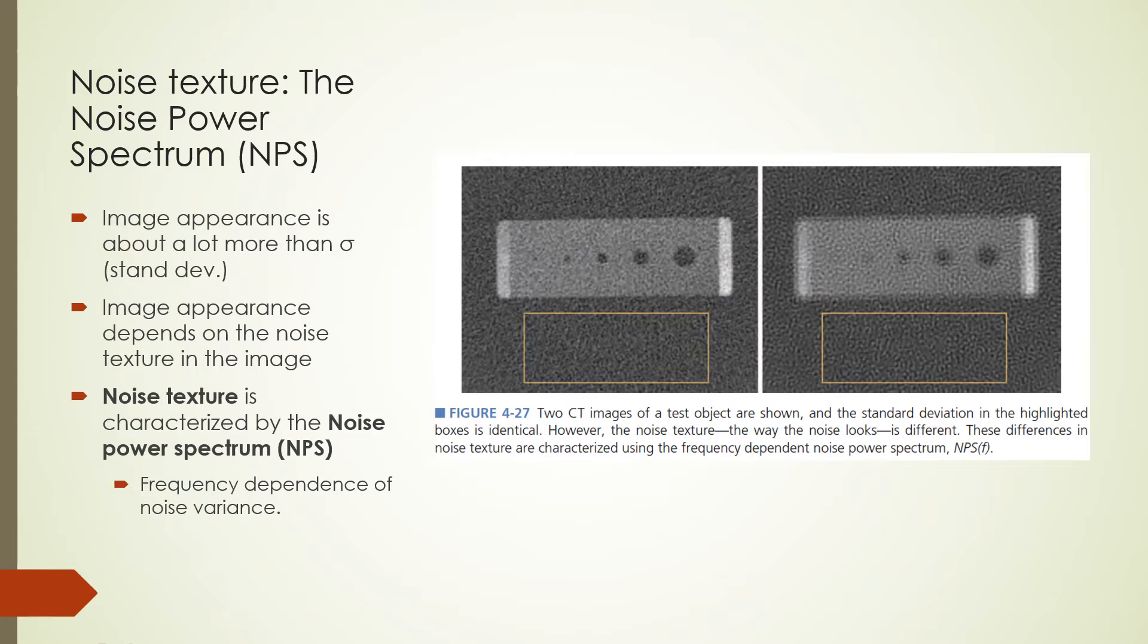On the previous slide, we looked at the noise magnitude in an image as the standard deviation of signal. That simple noise metric is not enough to characterize image noise. It turns out that the way noise looks is just as important as the noise magnitude. The appearance of the noise is called noise texture. Let's look at the two images on this slide. The standard deviations in the highlighted boxes are identical, but the noise looks different.